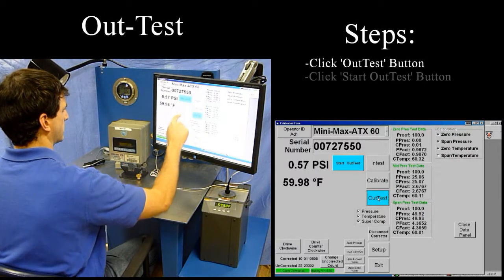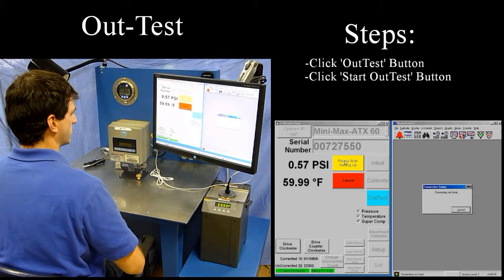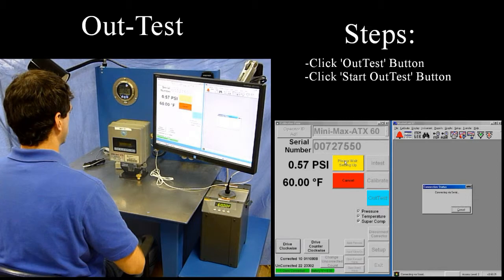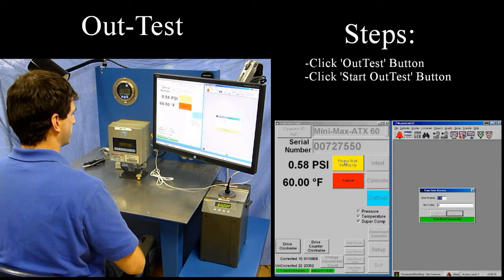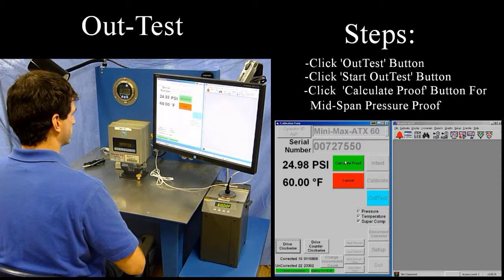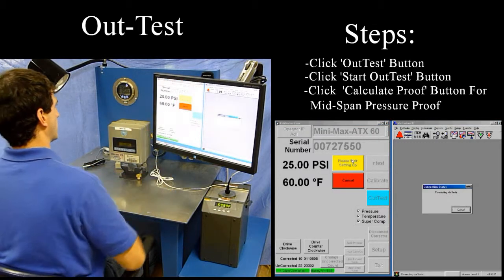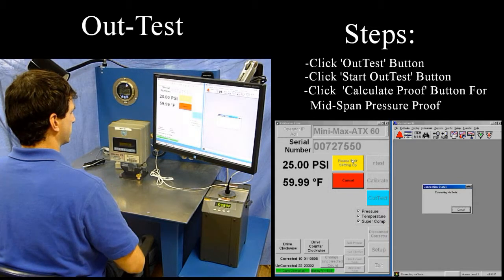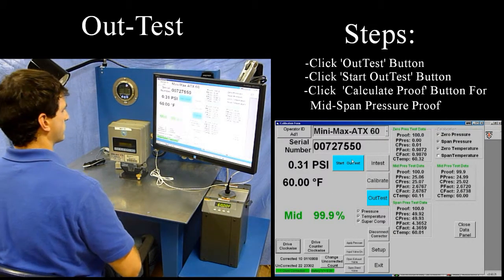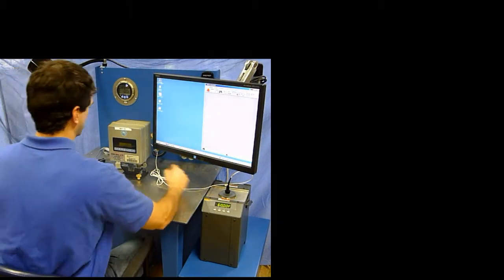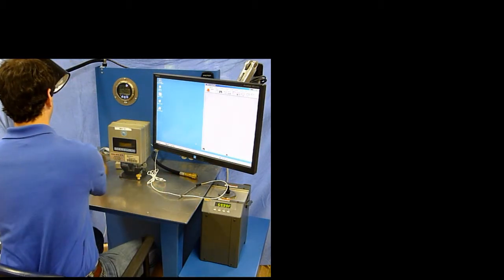To verify the calibration of the corrector, an out test can be performed. The test stand can perform a 3-point out test to ensure the calibration of the corrector. All data collected in both the in and out test, as well as the type of calibrations performed, are displayed in the data panel. If the instrument has an on-corrector modem, the user can test its operation using the stand's telephone line cable and built-in modem.